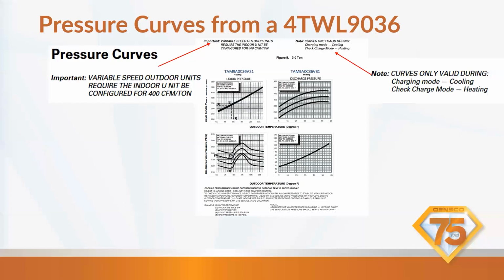Here's pressure curves. So we're kind of getting into what we want to see in heating. We're coming into heating season. Once I was taught to use these pressure curves, because we're going to be under 55-degree air, I've used these on other systems too. I mean, I've installed them all and fired off plenty, Lennox, Carrier, Coleman, Daikin, and I've used this graph. No other brand has these graphs with them, but these are critical to feeling comfortable about your refrigerant charge to eliminate some of the questions, right? And then the questions are what takes time.